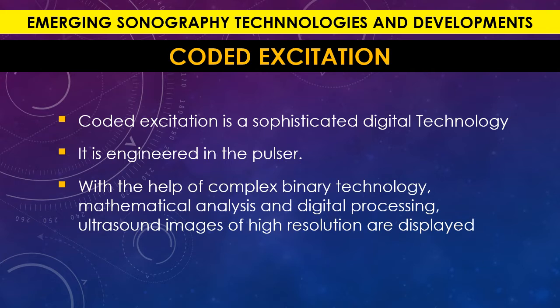It's engineered in the pulser. The pulser creates an electric voltage pulse that is made of multiple frequencies and is transmitted with a digital encoding. The ultrasound pulse that is created from the transducer has the same technology, which is encoded technology.